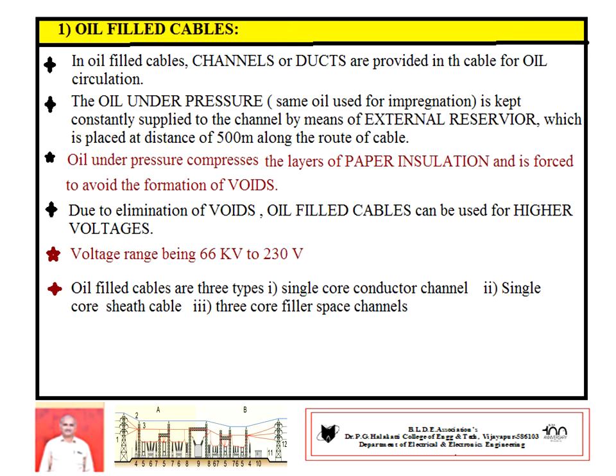In oil filled cables, channels and ducts are used for the circulation of oil. This oil is under pressure, and is constantly supplied to the channel or duct by an external reservoir. This external reservoir should be placed at a distance of 500 meters along the route of the cable. Some extra care should be taken. If we are using such type of cables, then we have to construct an external reservoir.